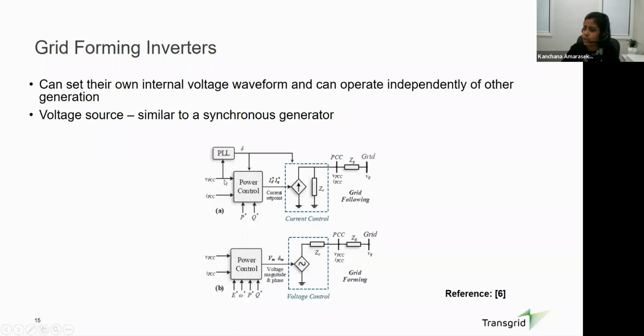This diagram tries to show you the difference between a grid following and a grid forming inverter. A grid following inverter demonstrates the characteristic of a current source. As I mentioned in the previous slide, they have a device called a PLL, which tracks the grid angle, and it injects currents to deliver the required power, so in general it demonstrates current source behavior. But grid forming inverters demonstrate voltage source behavior. So it is like a synchronous machine. They can set their own internal voltage waveform, and they can operate independently of other generation. It can form its own grid, in other words, and it's a voltage source similar to a synchronous generator.